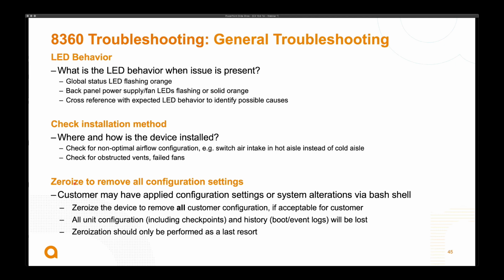Check the installation method. How has the device actually been installed? This can potentially be a cause of heat dissipation issues. If you have a non-optimal airflow configuration, let's just say you're doing back to front airflow, but the back of the rack is actually the hot aisle, not the cold, so the switch is sucking in hot air, that could be causing issues. If you have your vents obstructed, or any fan failure, those can also cause issues.